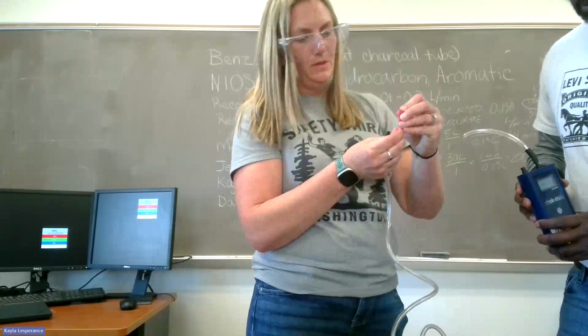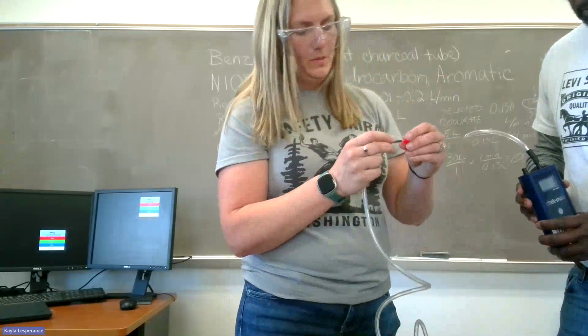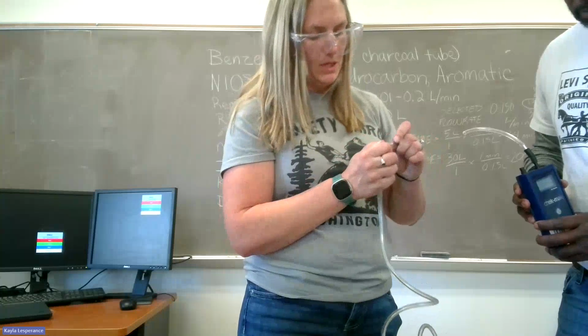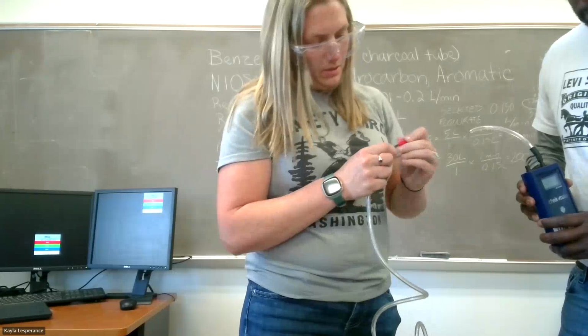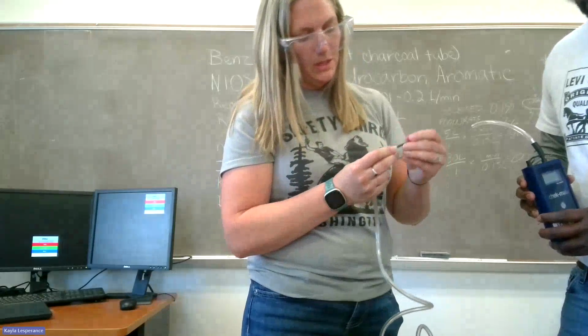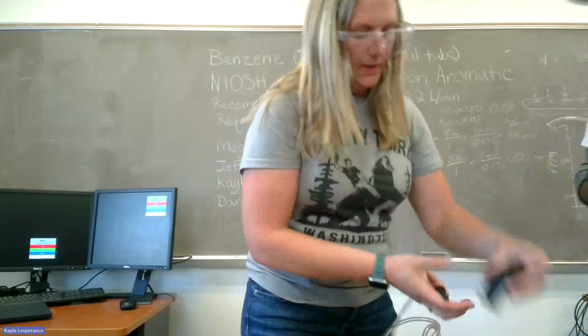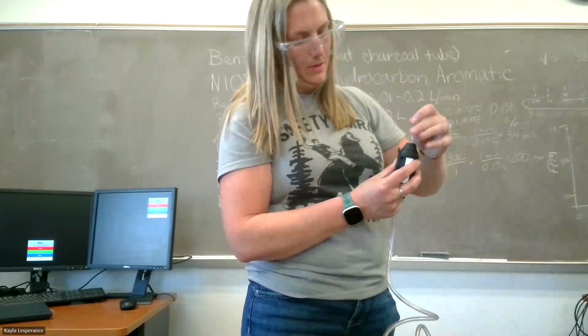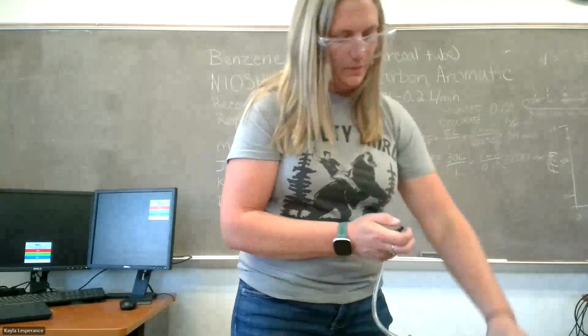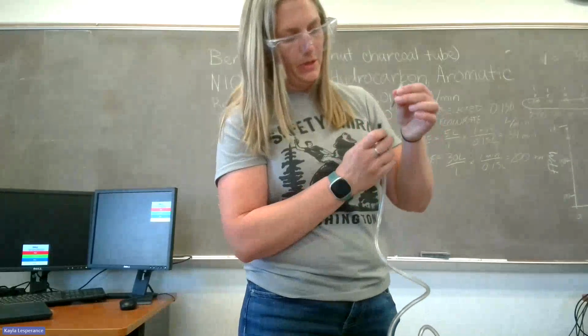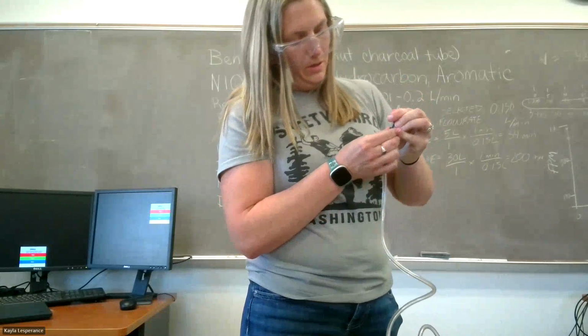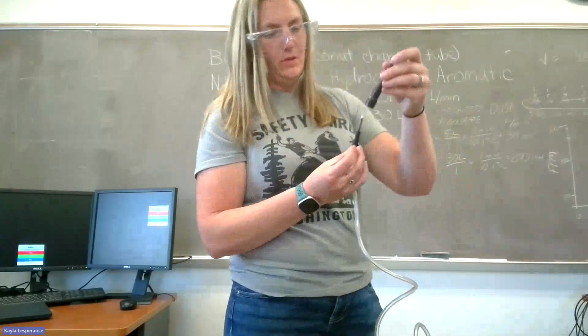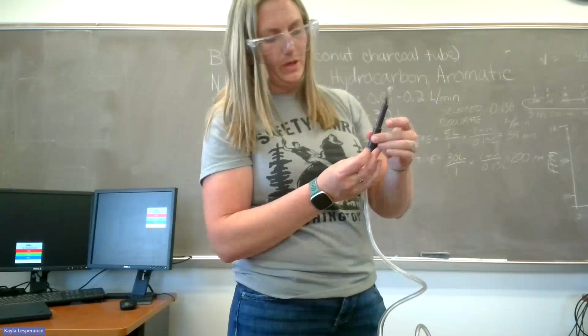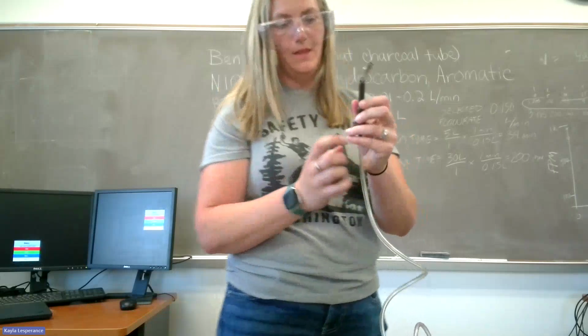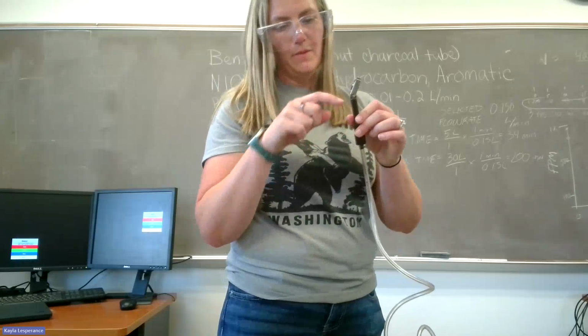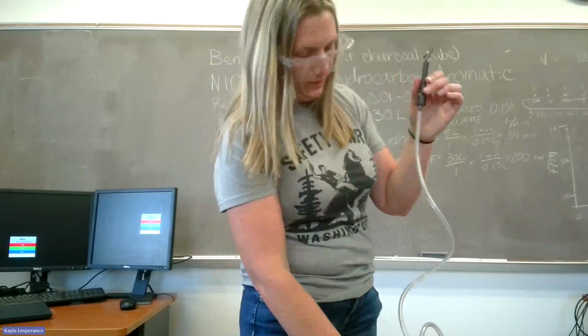So we have safety caps, end caps for these to protect anybody handling them from the broken tube edges. Bit of a wrestling match. Don't want to put those on too tight because you have to take them back off later. And then we'll grab our sample media, break the ends off that. And same thing, ensure the airflow is going the correct direction toward the pump. And then we have a safety cover that goes over the media to protect the worker from cuts or from the tube from breaking if it's hit on anything. The airflow goes in through the end of the safety cap. There's a little hole in there, so that's protected from getting clogged out also.